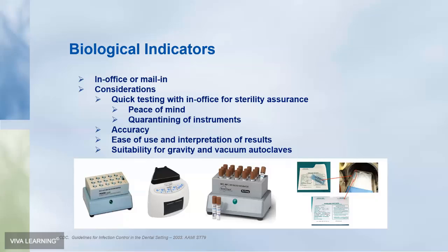One option is an in-office method, and the other is a mail-in. Some people like using a mail-in because it provides third-party verification. However, an in-office test provides you with much quicker results. Considerations then are quick testing within an office for sterility assurance. Again, peace of mind. You don't need to quarantine instruments for as long. So it allows you really to take control of your steam sterilizer testing. It lets you know there and then, almost, that your sterilizer is functioning properly, with more rapid results.